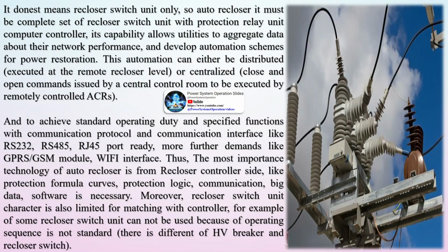high-voltage switchgear equipped with a protection relay controller to detect and interrupt momentary faults automatically. For overhead distribution networks, the majority of faults are transient, such as lightning strikes, surges or foreign objects coming into contact with the exposed distribution lines. By this logic, 80% of outages can be resolved by a simple close operation.